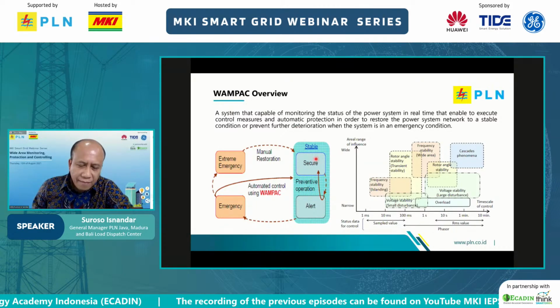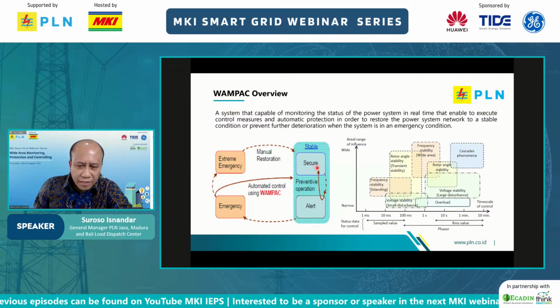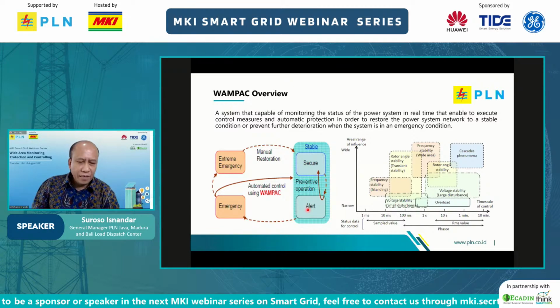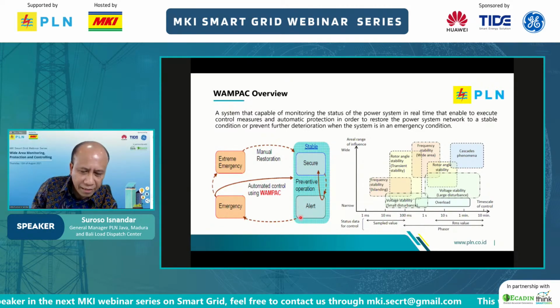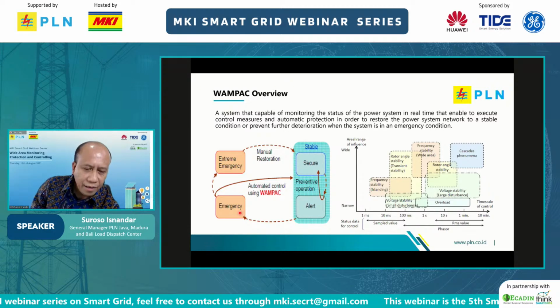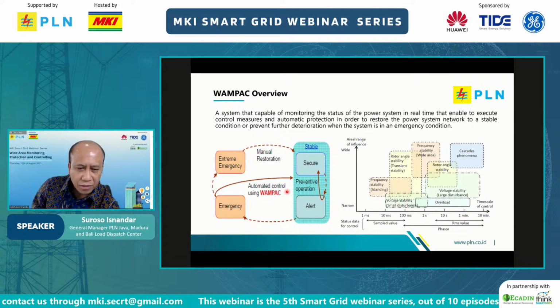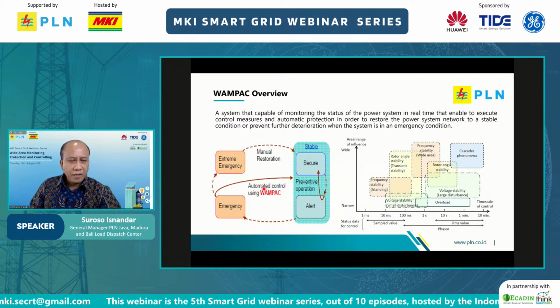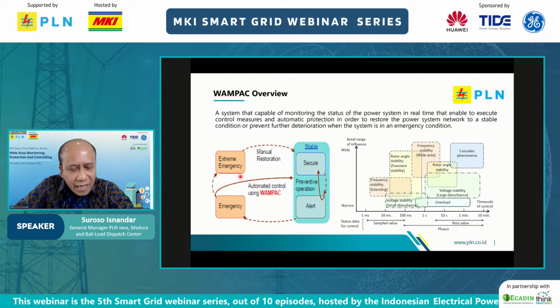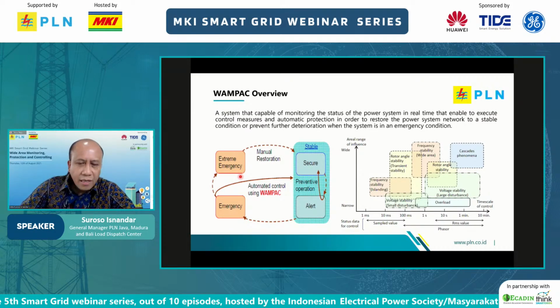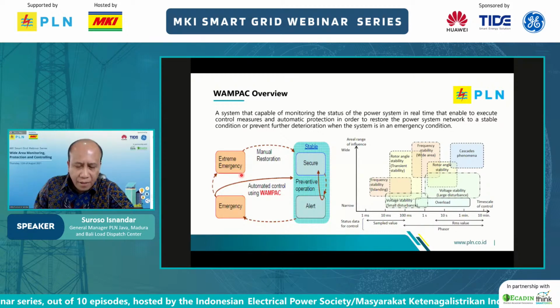Of course, on the normal time, the dispatcher has to keep the system stable and secure, but on unfortunate event, if the system moves into the alert position, we have to take a preventive measure. And also, if there is some more disturbance which brings the system into emergency, then we will have the automatic control measure using WAMPAC in order to bring back into the stable system, or even on the extreme emergency, it will help the manual restoration into the stability of the system.